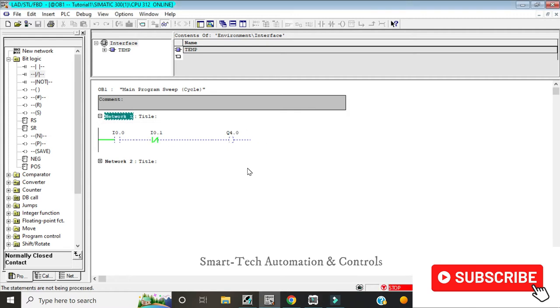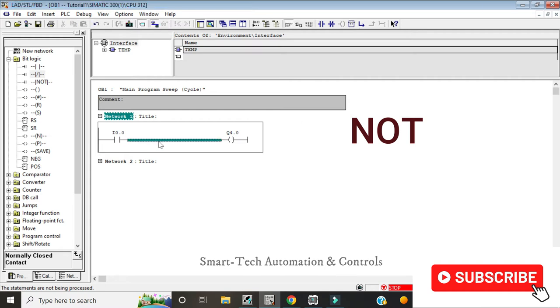We also have another bit logic, which is this one here, NOT, which acts as an inverter. Let's see how it works. For instance, if I have this diagram, then I introduce a NOT, you'll find that when there is no signal at this normally open contact, the output is energized. And when you give a signal to this input, the output becomes de-energized. And so this bit logic right here acts as an inverter. Let's simulate it and see.